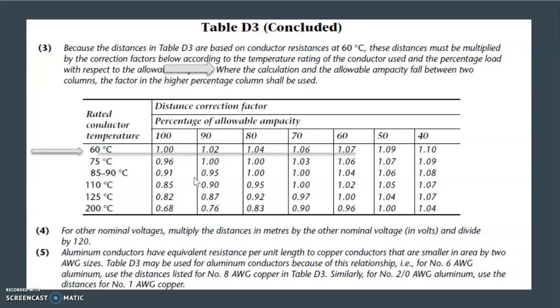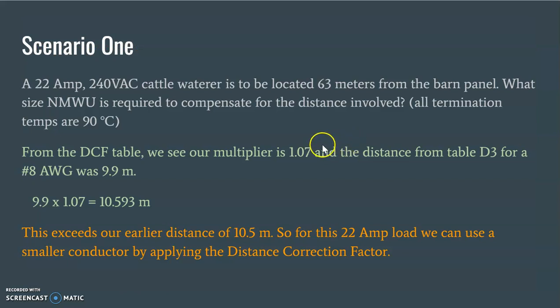So let's go back to the DCF table and take a look at that. So we go across here, percentage of allowable ampacity. Well, we don't have a 55. We have a 50 and a 60. Look up here at this bullet point—that's not a bullet point, I just put an arrow there. It says where the calculation and the allowable ampacity fall between two columns, the factor in the higher percentage column shall be used. So it tells us that we just go to the next higher column when it falls between two of these values. Even if it was 51 percent, we'd go to the 60. Our rated conductor temperature again is 60. We go across here until we get to this value here. So this becomes our multiplier. So we have our multiplier, and we know what our distance from Table D3 is for a number 8 is 9.9. 9.9 times 1.07 works out to 10.593 meters.